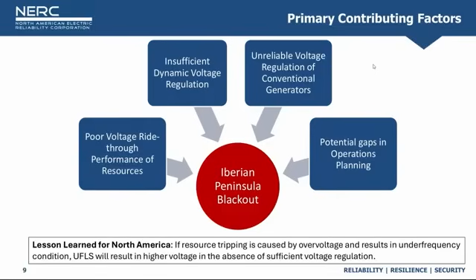And in hindsight, if operators understood how fragile the system was, they could have planned for additional dynamic voltage support from other plants early on and have them spun up and ready to go. However, once they realized there was an issue, even though they ordered conventional generators to start, they didn't have time to get them online. So the lesson learned for North America is that if resource tripping is caused by overvoltage and results in under-frequency conditions, under-frequency load shedding would result in higher voltages in the absence of sufficient voltage regulation. Next slide. Some of the measures that we've worked on here is just trying to see what we're learning from this outage.